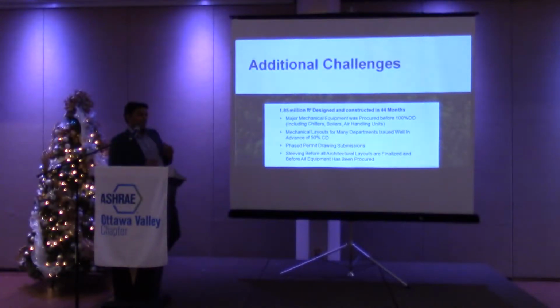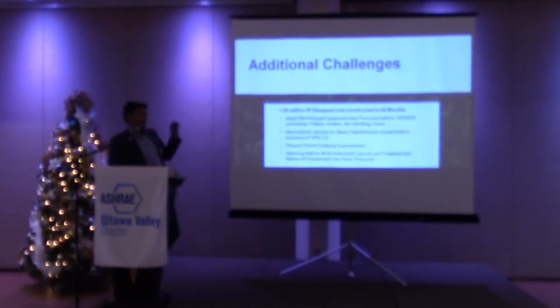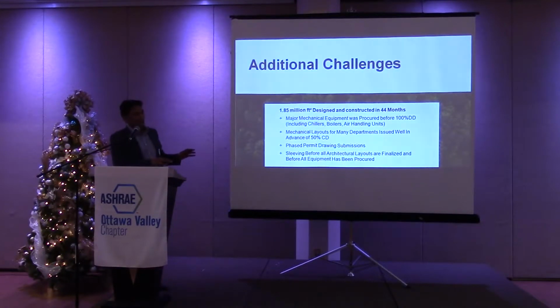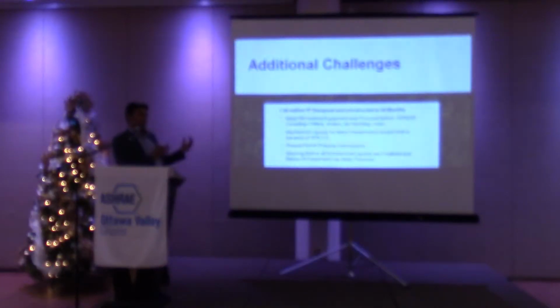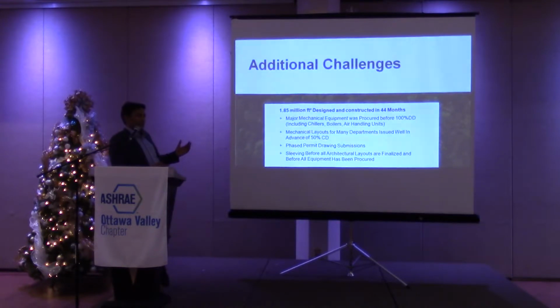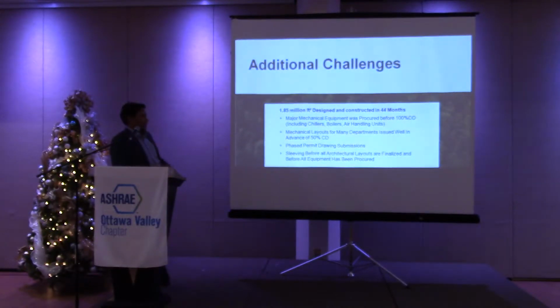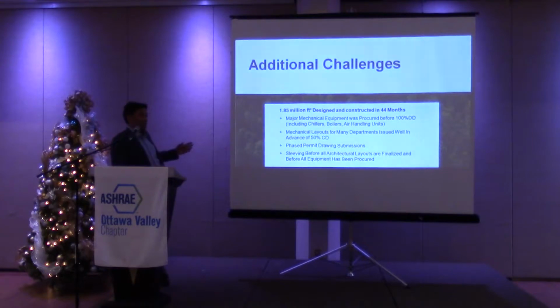We had suppliers fill out a spreadsheet plugging in what their fan energy requirements were for the air handling systems to spit out a final number that took into account the operating hours of each air handler. So you could build one box a little bit bigger and use a little bit less energy, another air handler a little smaller, use a little bit more energy, but if the smaller box that was using more energy only ran 8 hours a day versus the other one ran 24 hours a day, you could offset that energy balance.